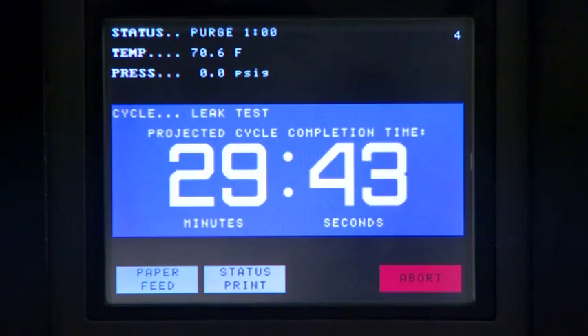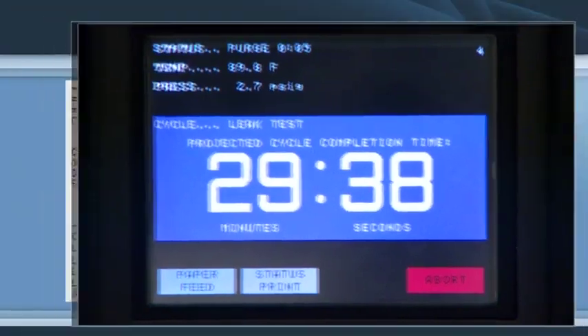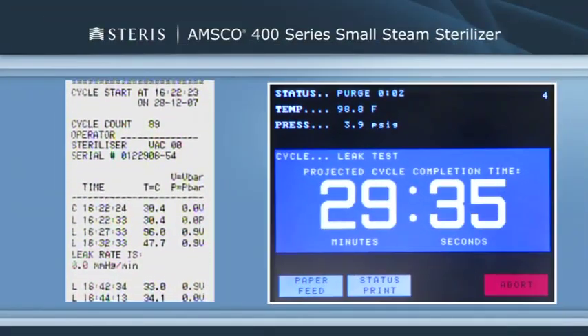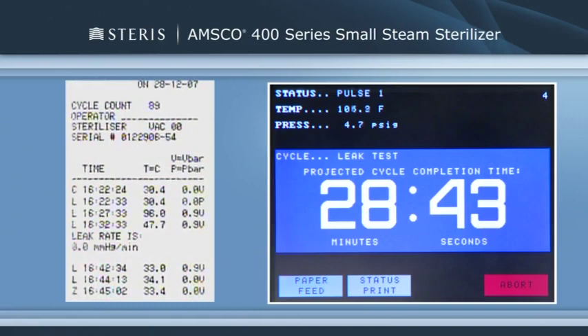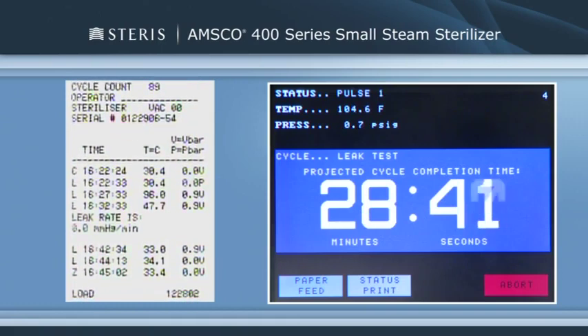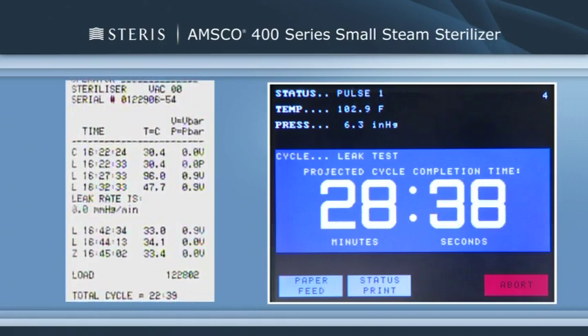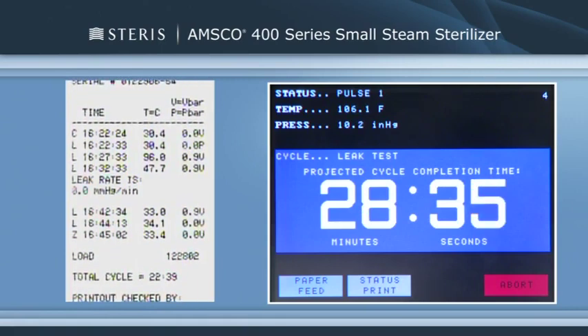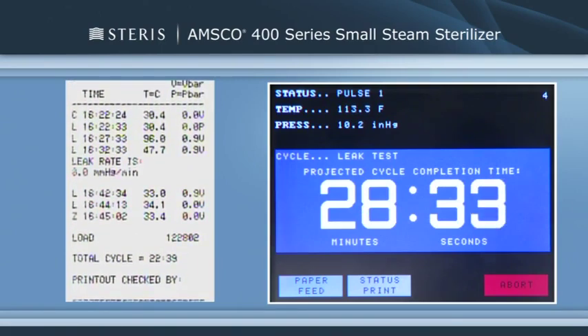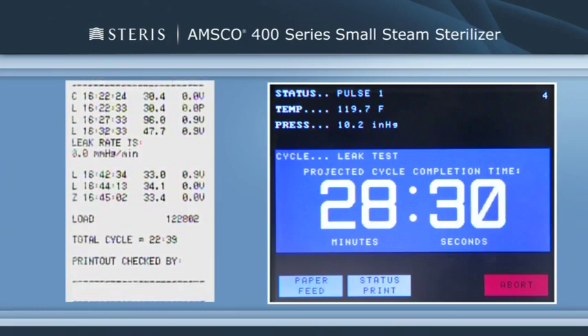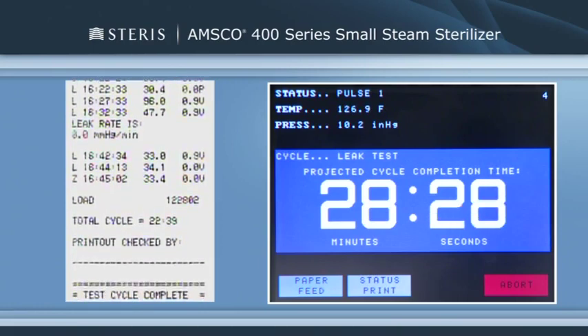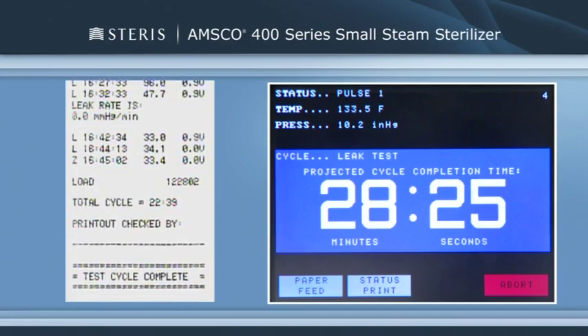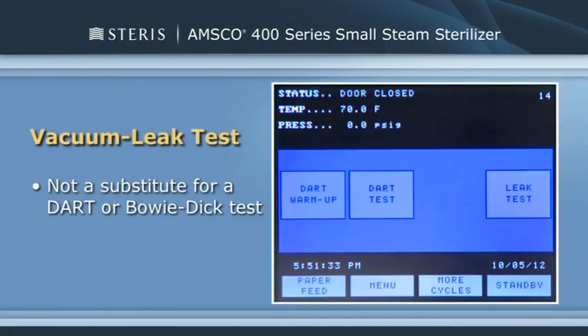Again, the vacuum leak test cycle values are pre-programmed and cannot be adjusted. The entire vacuum leak test cycle is also documented on the printout and includes a leak rate value. A leak rate of less than 1.0 millimeters of mercury per minute is considered acceptable. Leaks greater than this need to be addressed by service or maintenance personnel, who can monitor the airtightness of the system and make repairs or adjustments as needed. Only SFPP and gravity cycles should be run if the leak rate is greater than 1.0 millimeters of mercury. It's important to note that the vacuum leak test is not a substitute for a Dart or Bowie-Dick test.